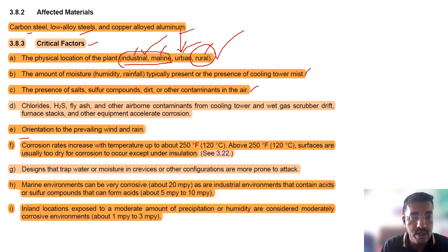Corrosion rate increases with temperature up to 120 degrees centigrade. This is very important. Above 120 degrees centigrade, surfaces are usually too dry for corrosion to occur, except under insulation. So above 250 F or 120 degrees C, the corrosion usually stops. Below that temperature, usually corrosion happens. Why? Because the surface is dry after 120 degrees centigrade. Possibility is there if there is insulation.